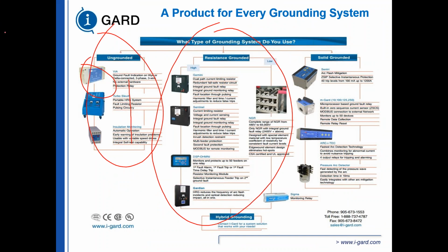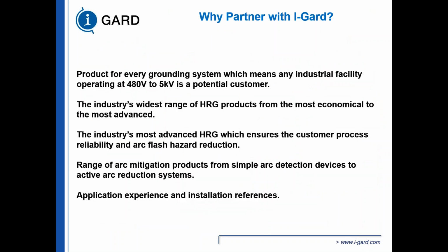And for solidly grounded systems, we have ground fault protection relays that can go up to 1200 amps, arc flash mitigation systems, pressure switches, and ground fault monitors.